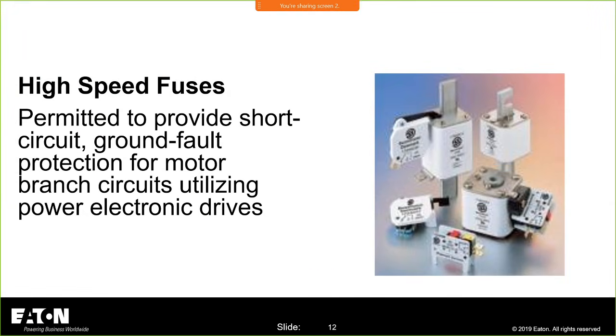That is not how we do things in the high-speed fuse world, because when you're applying a high-speed fuse, you're looking at the I squared t let-through, how much energy you are going to let into the system. That's how they determine what high-speed fuse to select. That was an interesting thing. I sat on the help desk for a while, and that's when you really learn, is when you're taking 800 number calls and you're trying to help people pick the right fuses. That's when I really learned a lot about high-speed fuses. And that is short circuit protection, ground fault protection, etc. Again, power electronic drives. This is going to reduce the damage inside. They are very fast-acting devices.